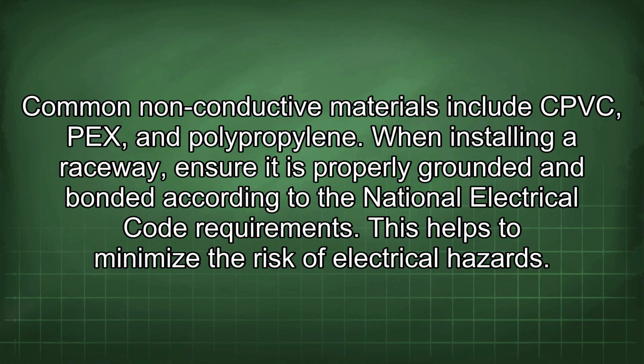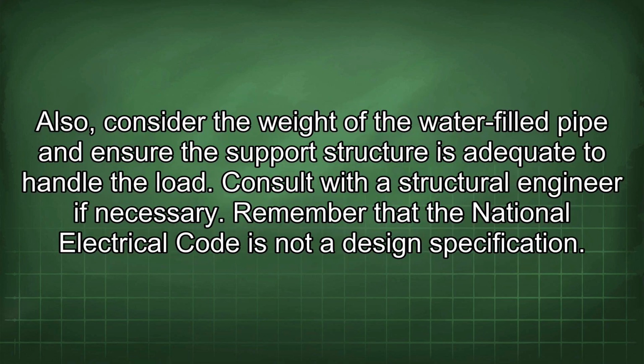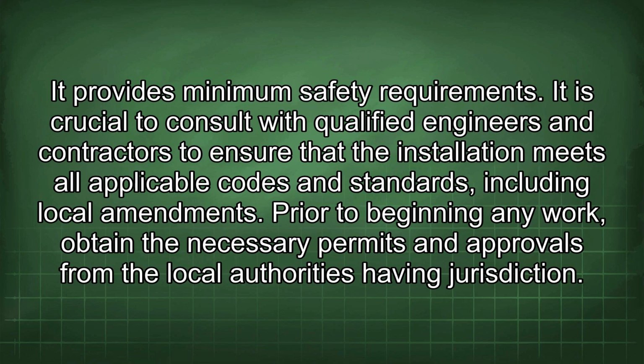When installing a raceway, ensure it is properly grounded and bonded according to the National Electrical Code requirements. This helps to minimize the risk of electrical hazards. Also, consider the weight of the water-filled pipe and ensure the support structure is adequate to handle the load. Consult with a structural engineer if necessary. Remember that the National Electrical Code is not a design specification. It provides minimum safety requirements.